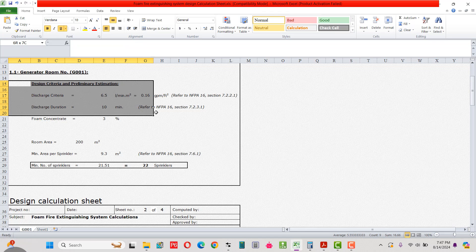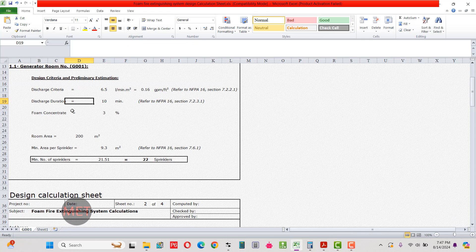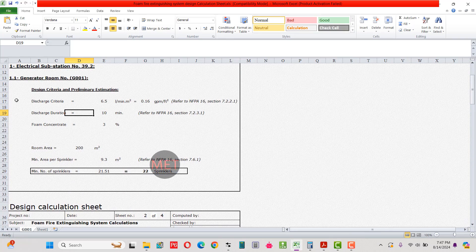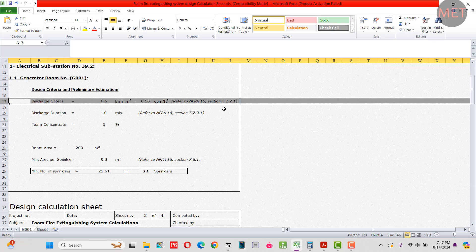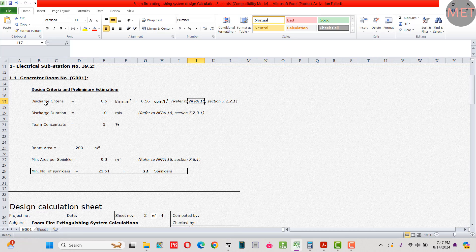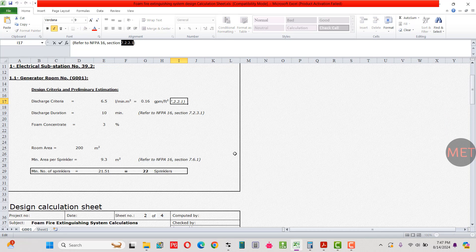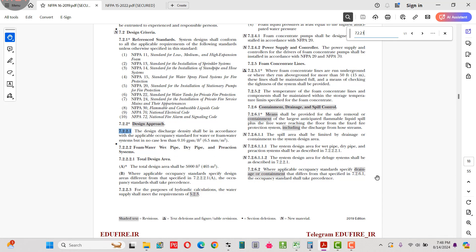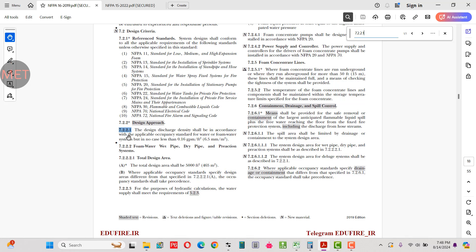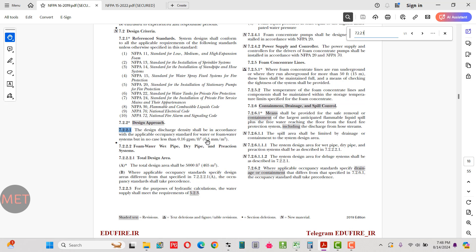The first input is the discharge criteria, which is 6.5 liters per minute per square meter, equal to 0.16 GPM per square foot, as per NFPA 16 section 7.2.2.1. Looking at that section: the design discharge density shall be in accordance with the applicable occupancy standard, but in no case less than 0.16 GPM per square foot or 6.5 liters per minute per square meter.